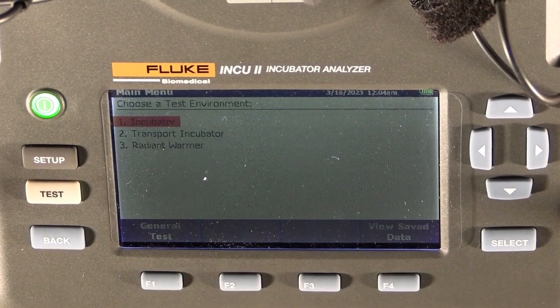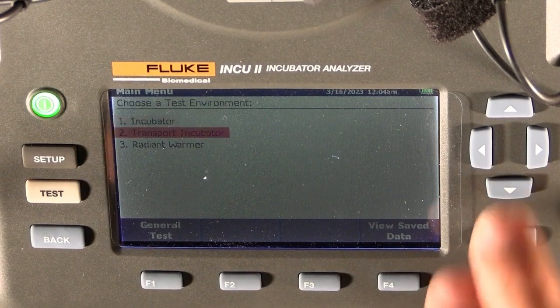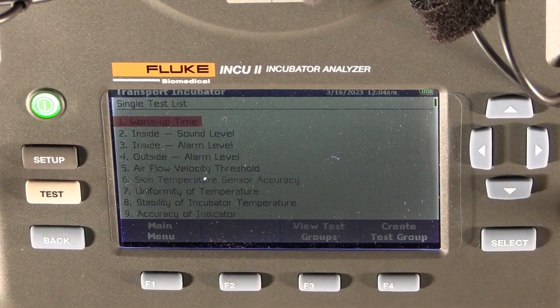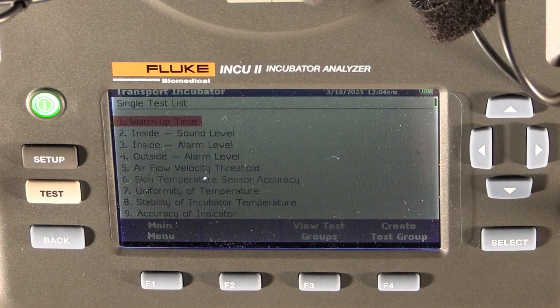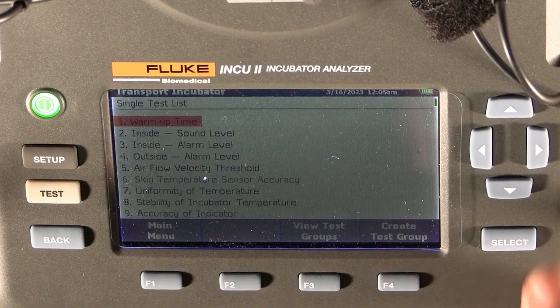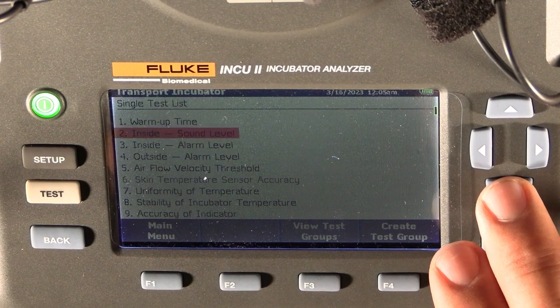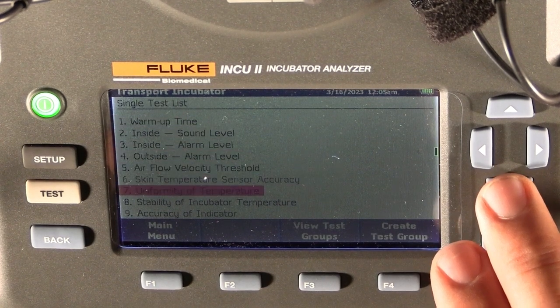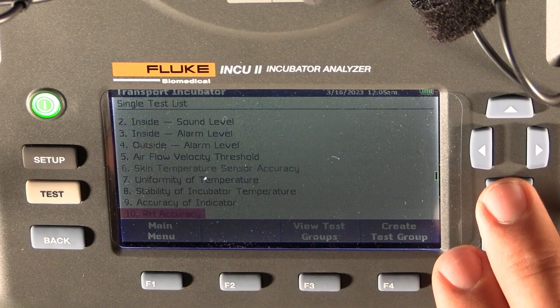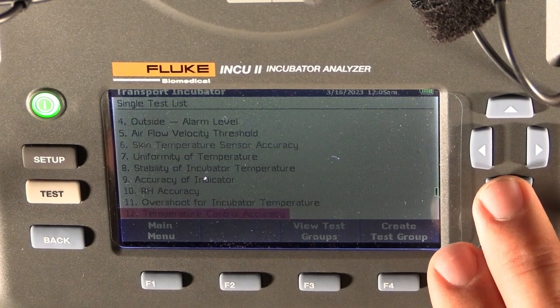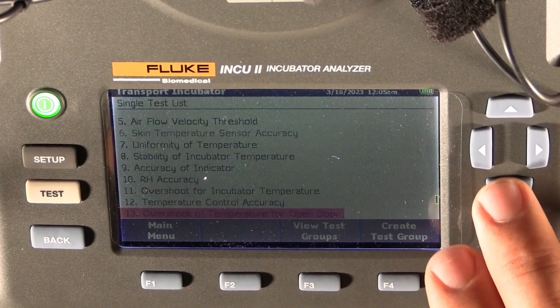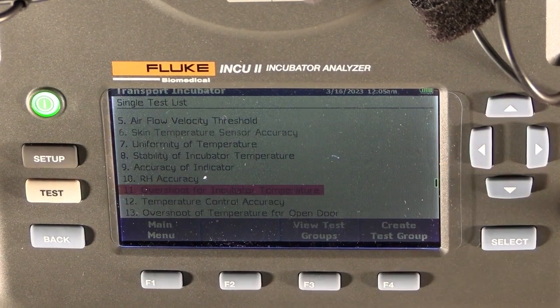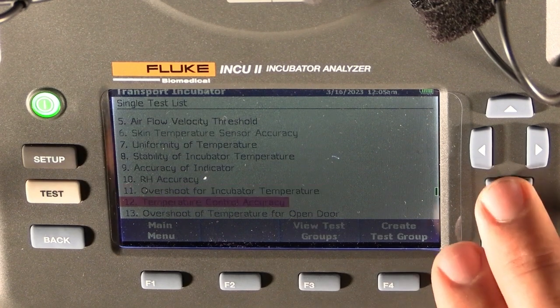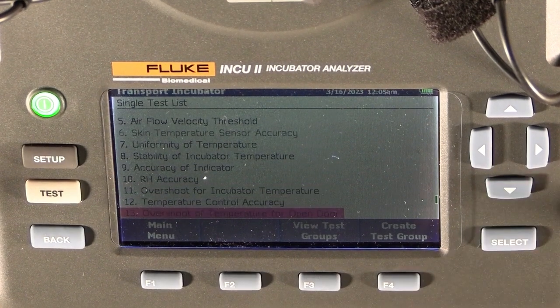If we go back to the main menu, we can then go to transport incubator and press the select button. In the transport incubator, you will see that we've got pretty much the same list as in the normal incubator. If I go down to them, you'll see the only difference is that we've got the normal overshoot temperature measurement like we've done in the normal incubator, but then we have an overshoot of temperature for open door.